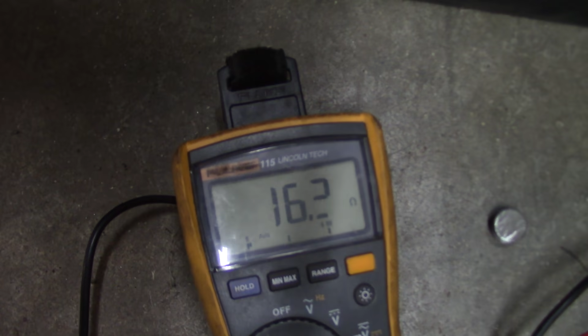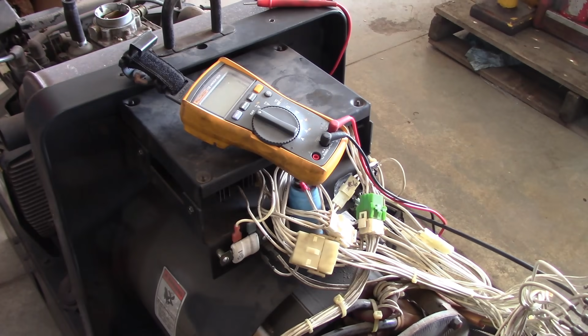Alright, so we only got 13 volts across the exciter field. Should be 50 volts DC. And if I measure the resistance across that exciter field, it's supposed to be 12.3 ohms, and I'm getting 16.2. So that's the only thing I've found so far that's out of spec.